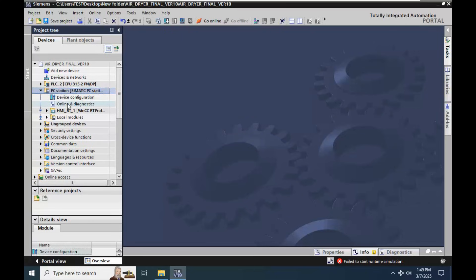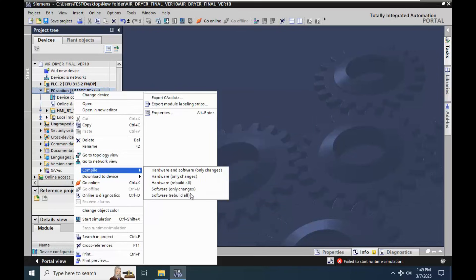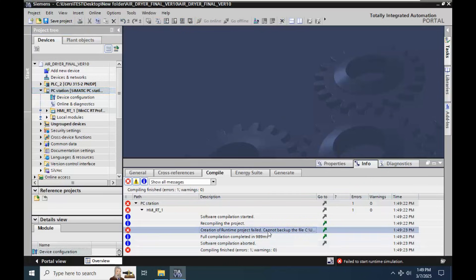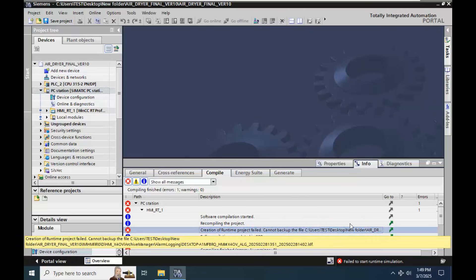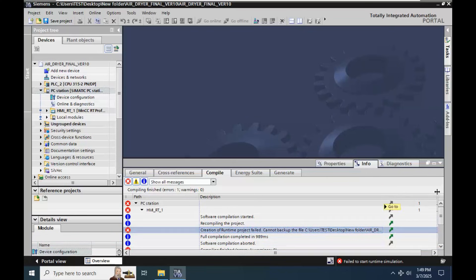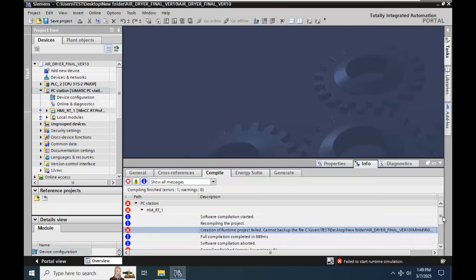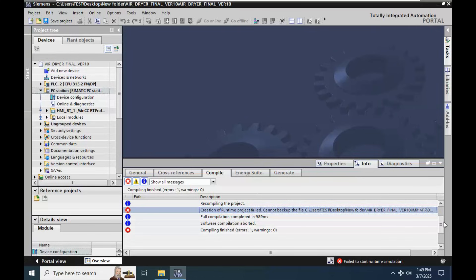Let me just compile the station — rebuild all software. It's possible to see that we have this alarm: 'Creation of runtime project failed. Cannot backup the file.' This is a file regarding the LDF, which relates to the SQL server.